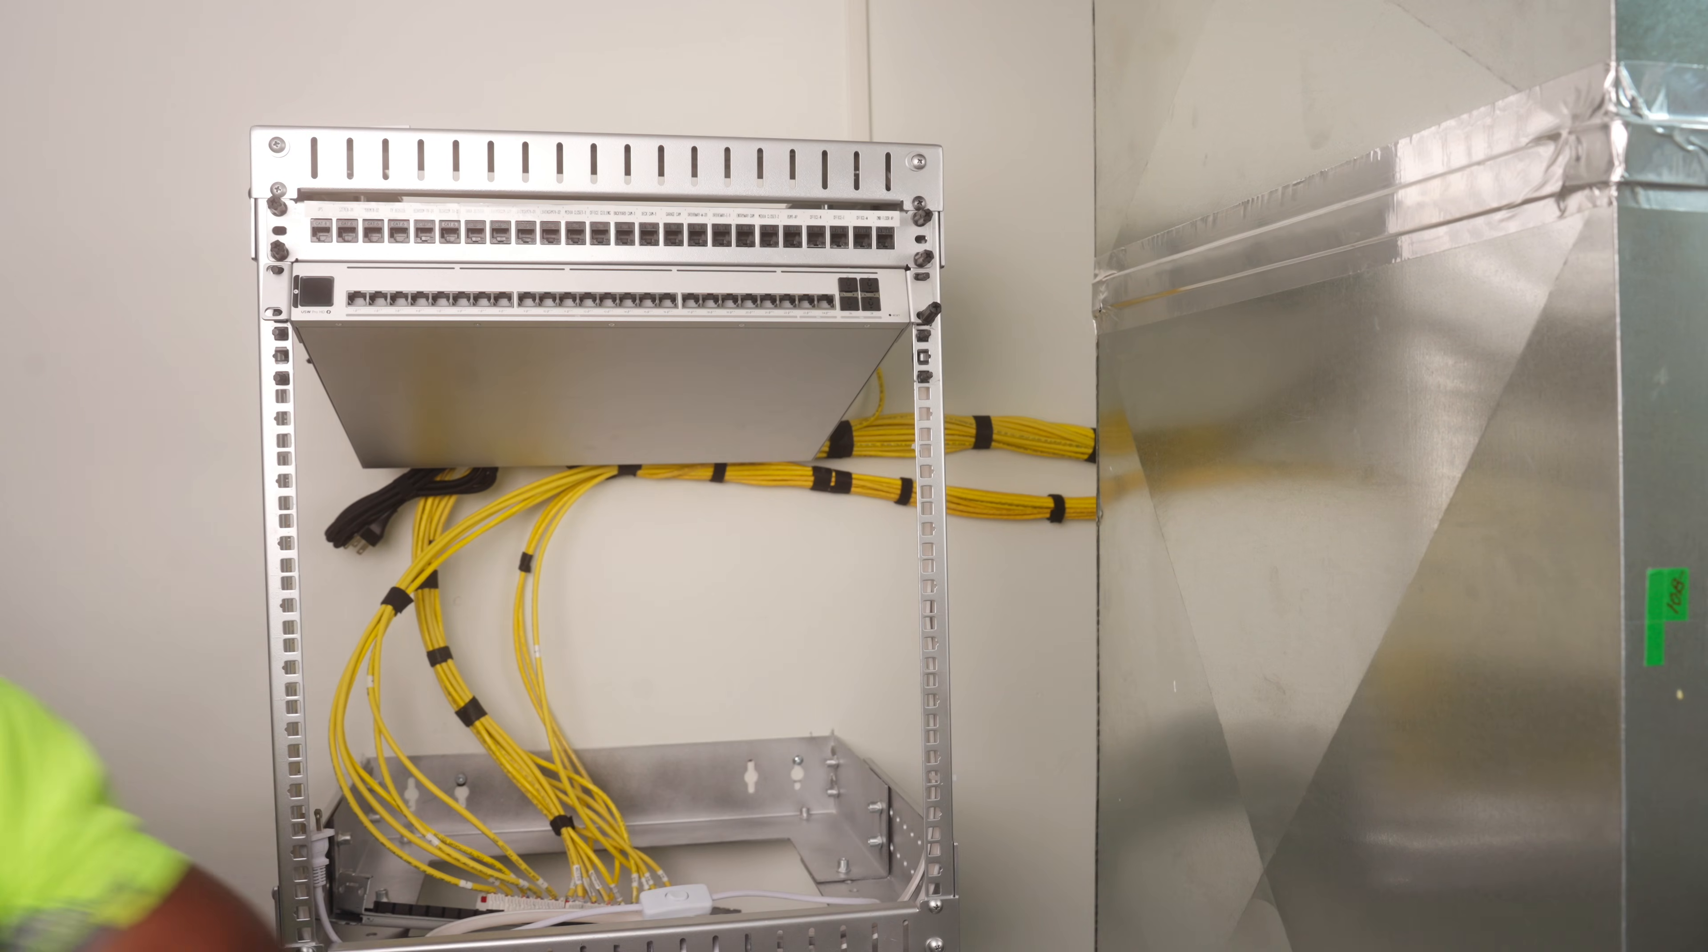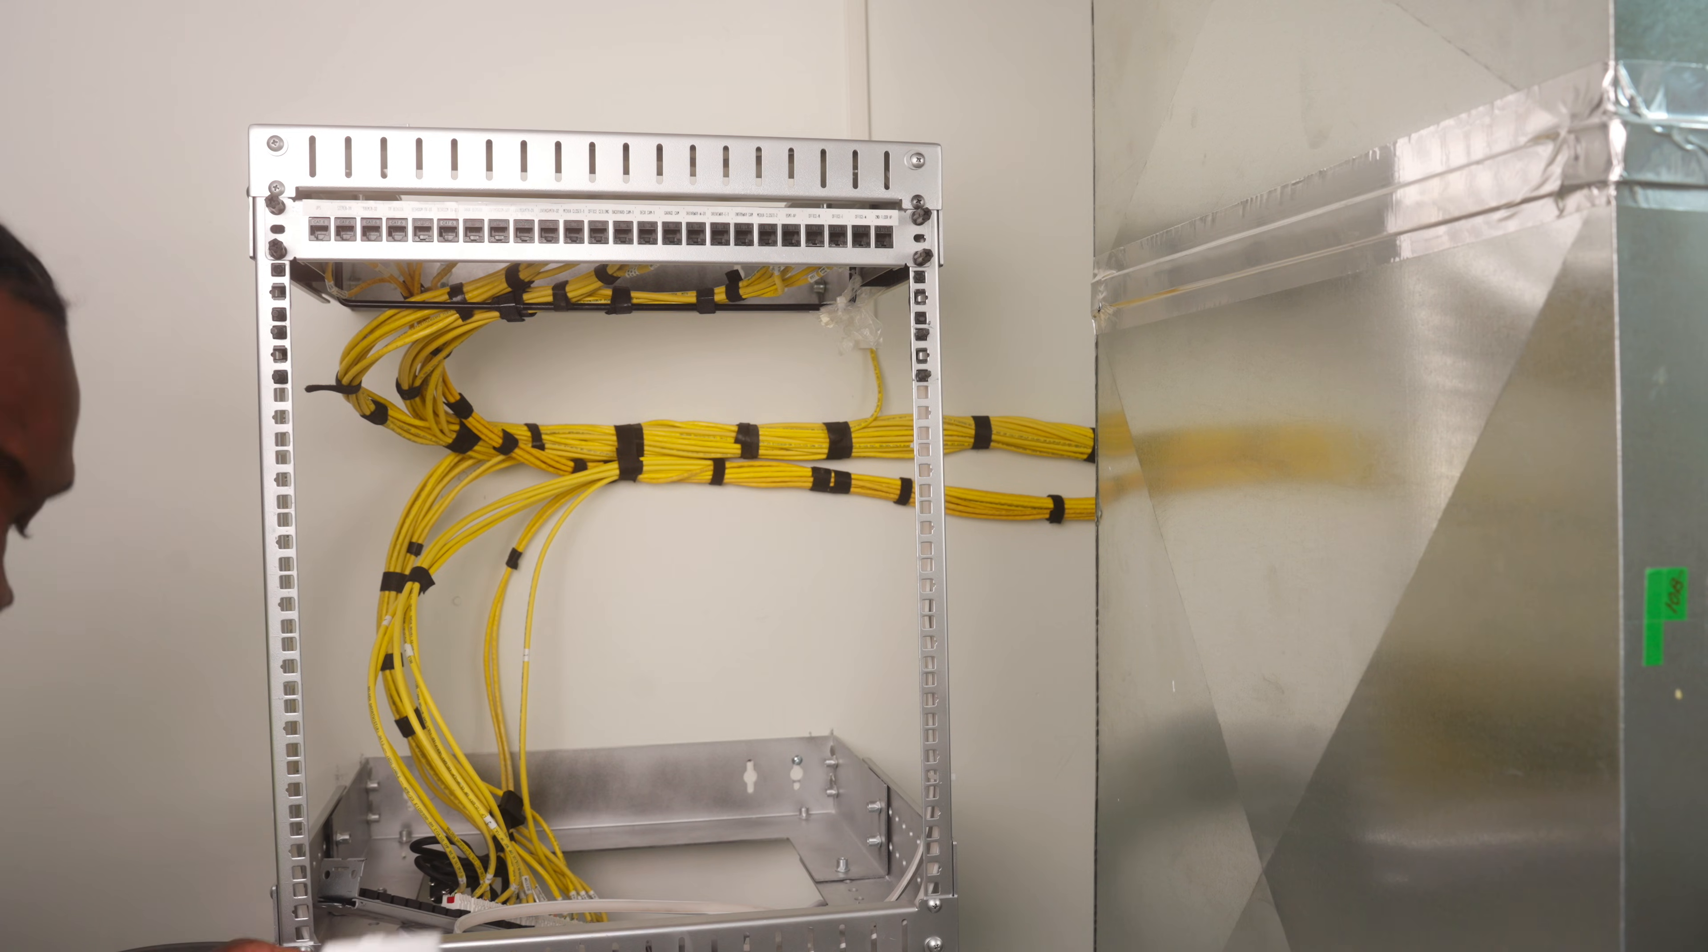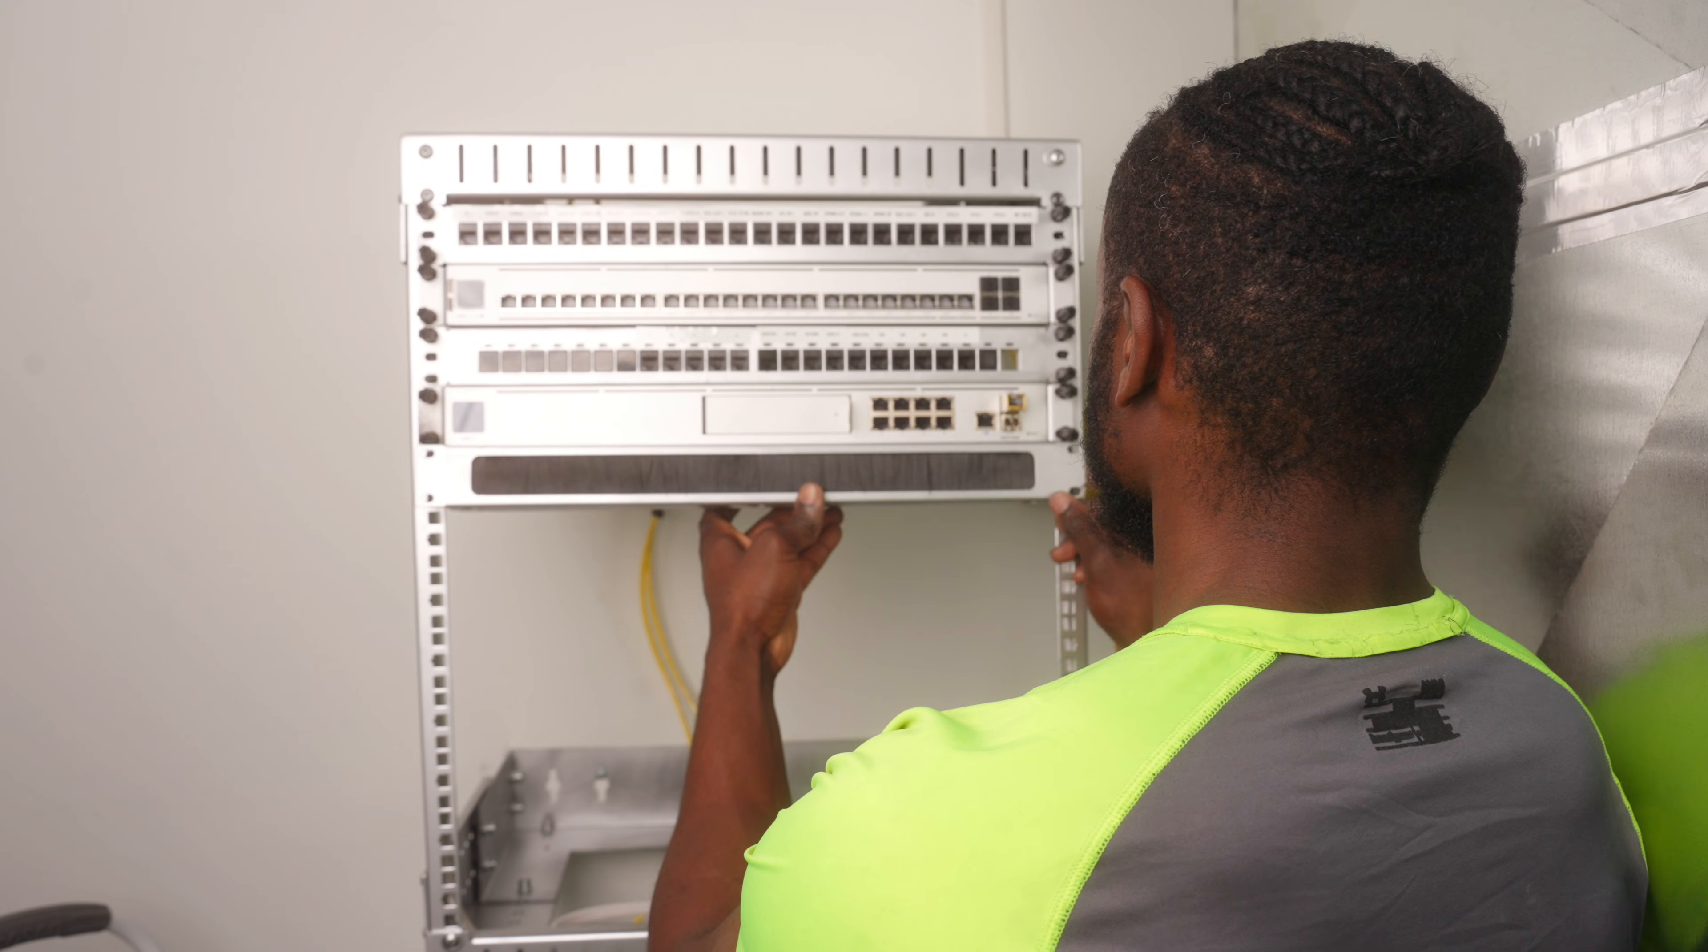While adjusting my cable bundle, one of the studs snapped and the switch dropped. The cable bundle above was strapped too low, pulling downward pressure on the back. I should have fixed the bundle first—lessons learned. Even with this mishap, I still prefer rack studs for light gear.